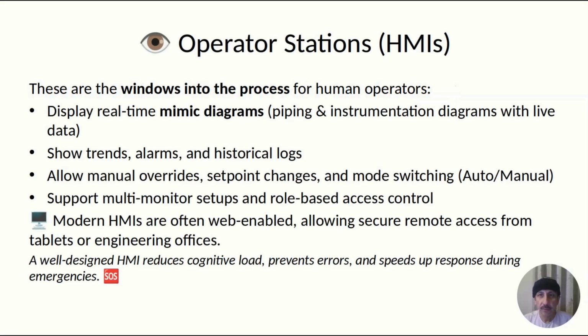Operator stations, human-machine interface, with the acronym HMI. Operators don't stare at raw data. They interact through HMIs, which are graphical interfaces that turn thousands of data points into intuitive visuals. A well-designed HMI shows a live P&ID, which is piping and instrumentation diagram, with color-coded pipes, animated valves, and real-time trends. Alarms pop up with clear priorities, no more alarm floods.